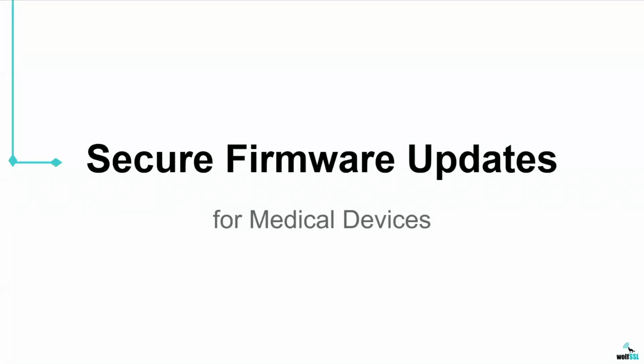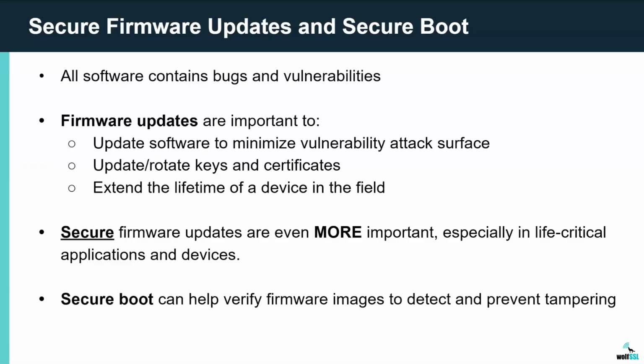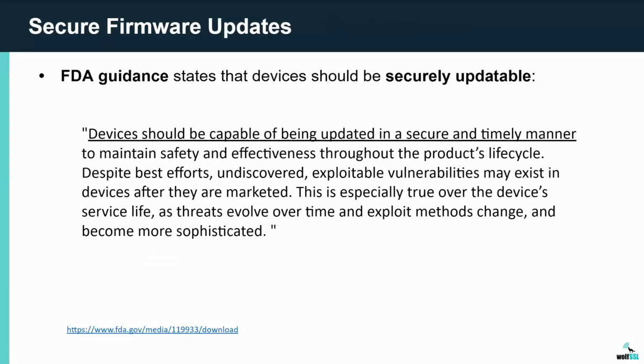So another critical feature for medical devices are secure firmware updates. Given that all software inevitably contains bugs and vulnerabilities, a mechanism for updating software to address these issues is essential. Firmware updates can also be utilized for things like rotating keys and certificates, which can potentially extend a device's lifespan in the field. While firmware updates are beneficial, secure firmware updates are even more advantageous, especially in life-critical applications, as they allow for authenticating the source of the binary blob and detecting any tampering. As you'll recall, the FDA guidance document had recommendations that devices should be capable of being updated in a secure and timely manner.